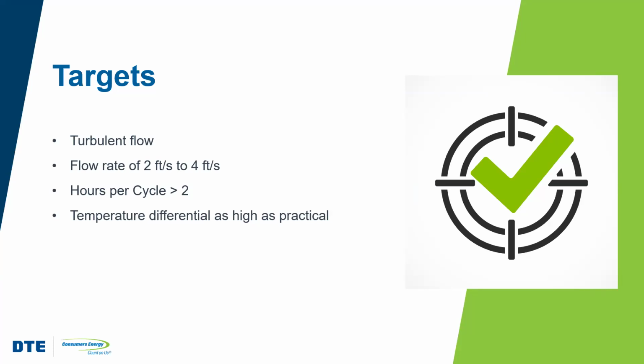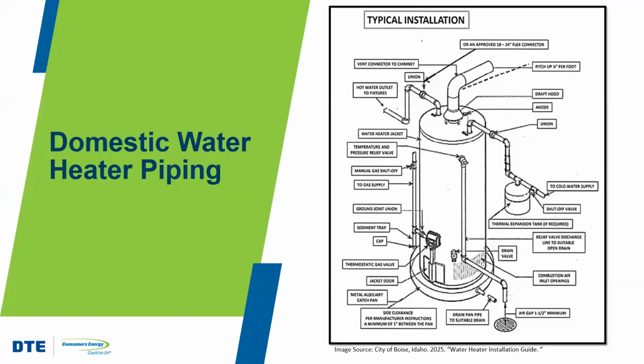We don't want a lot of noise and things like that. But with hydronic systems, we want that turbulent flow because we want that good temperature mixing. We also want to design for flow rates between 2 and 4 feet per second through the system. And we want the hours per cycle to be greater than 2, right? Bigger is better in this particular case. But we want it to be definitely greater than 2. And we want that temperature differential, again, to be as high as practical.